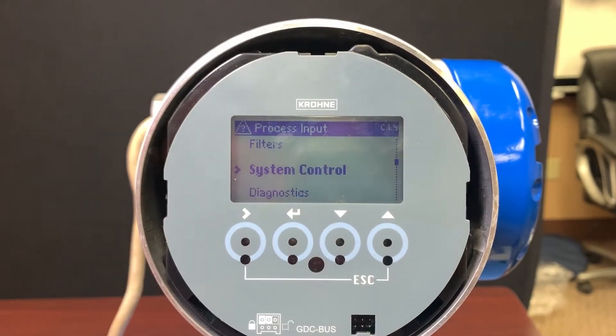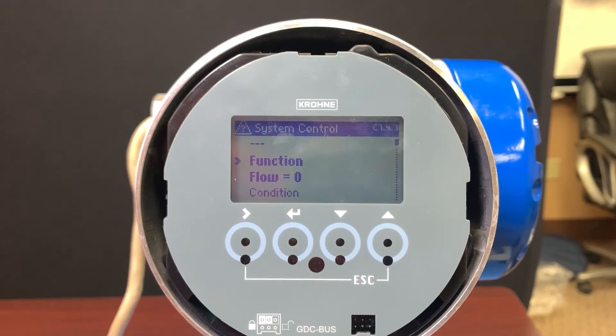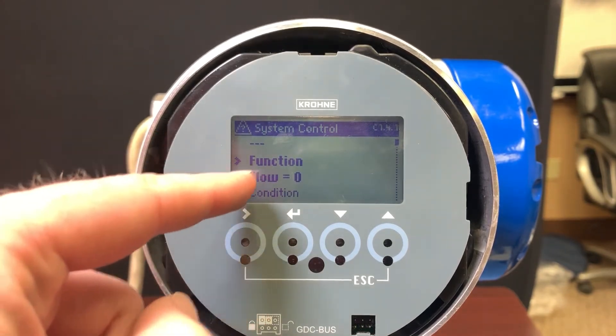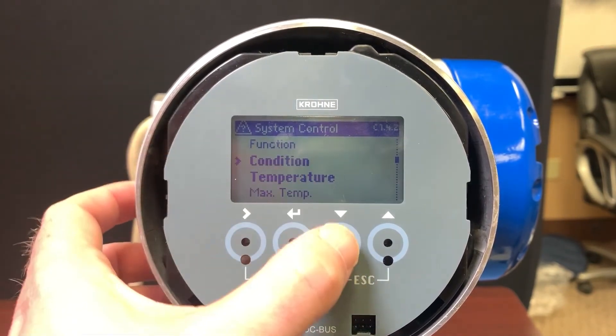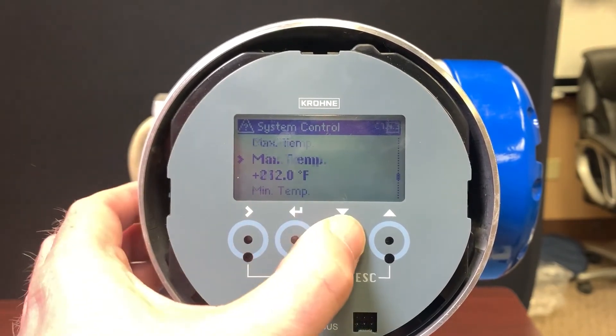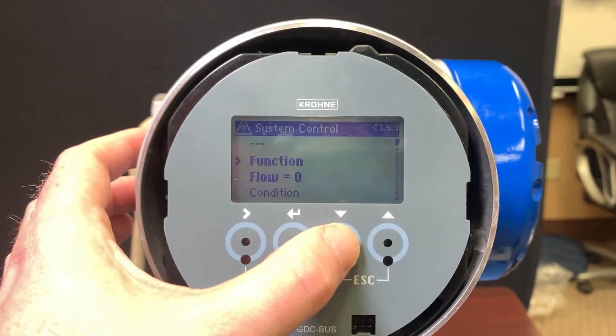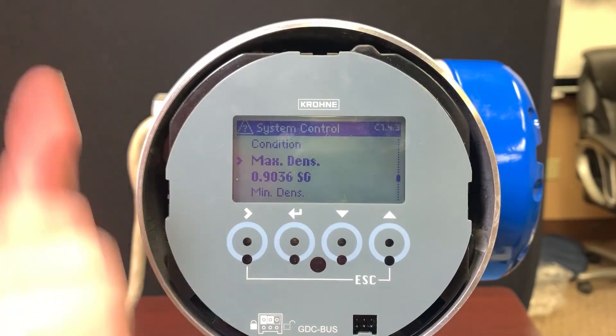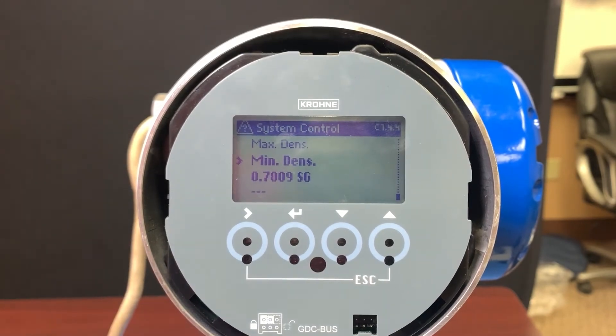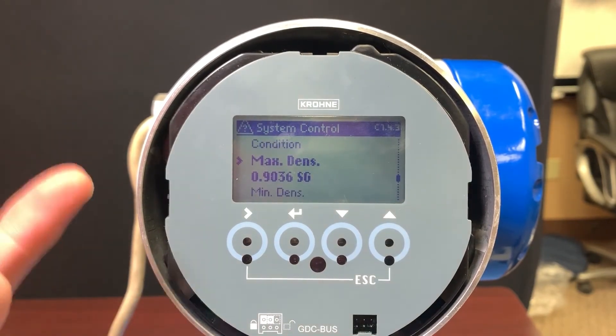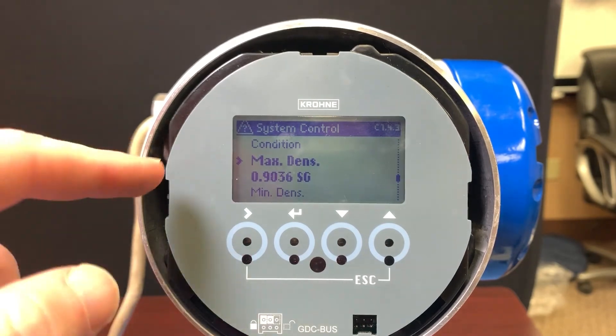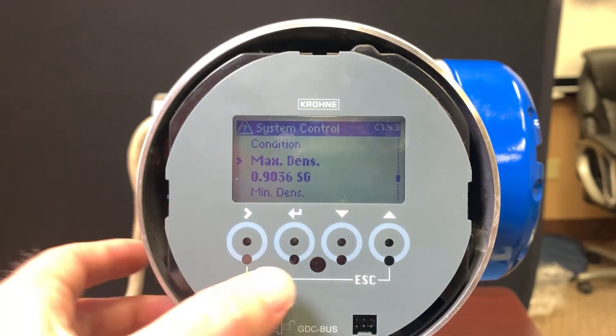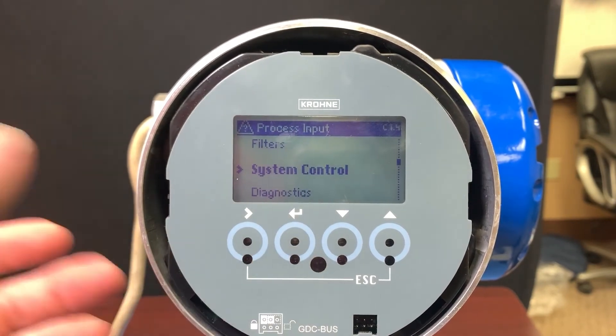System control is another pretty neat function. It gives us a way to create a windowed condition where the meter won't read. In this case we're saying make flow zero if the temperature is above 212 or below 32. I've used this for density in the past — in gravity, if my density was above 0.9 or below 0.7 I don't want it to measure. In oil and gas you may not want to measure water, so you can find a balance point during your dump cycle where this number helps you filter out water and just keep track of oil.